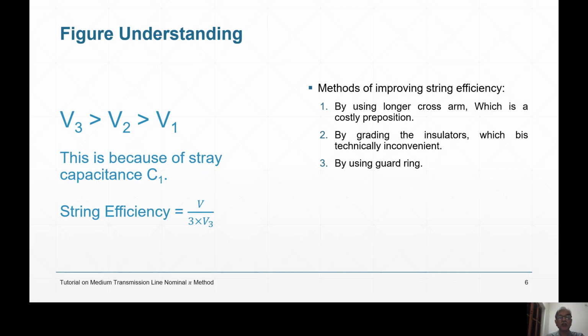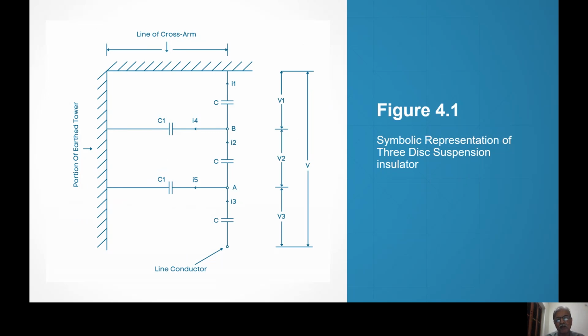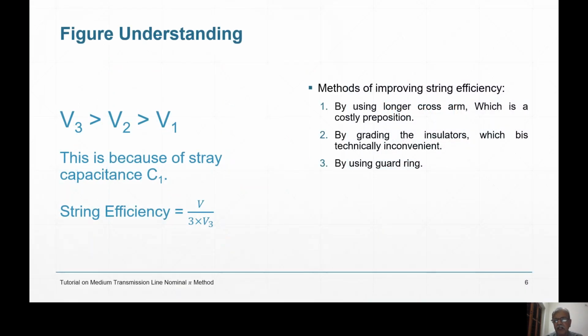So because of stray capacitance, the problem comes. What is the value of V3? What is the value of V2? What is the value of V1? You can calculate these if you know the value of stray capacitance C1, or if you can measure it. The shunt capacitance the manufacturer of the insulator will tell you. So knowing all these things and the voltage at which you are going to use the line, you can always calculate everything.